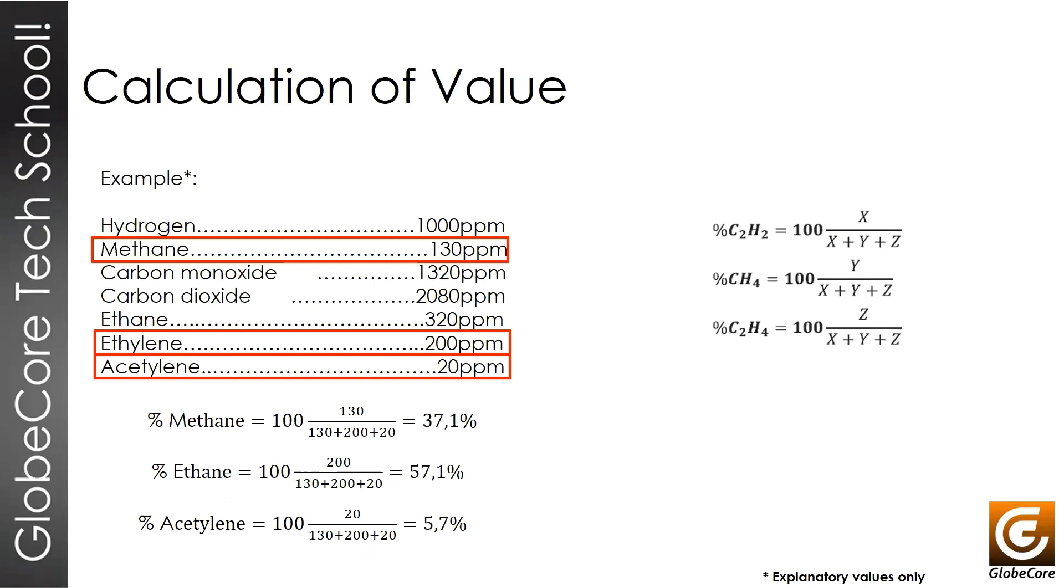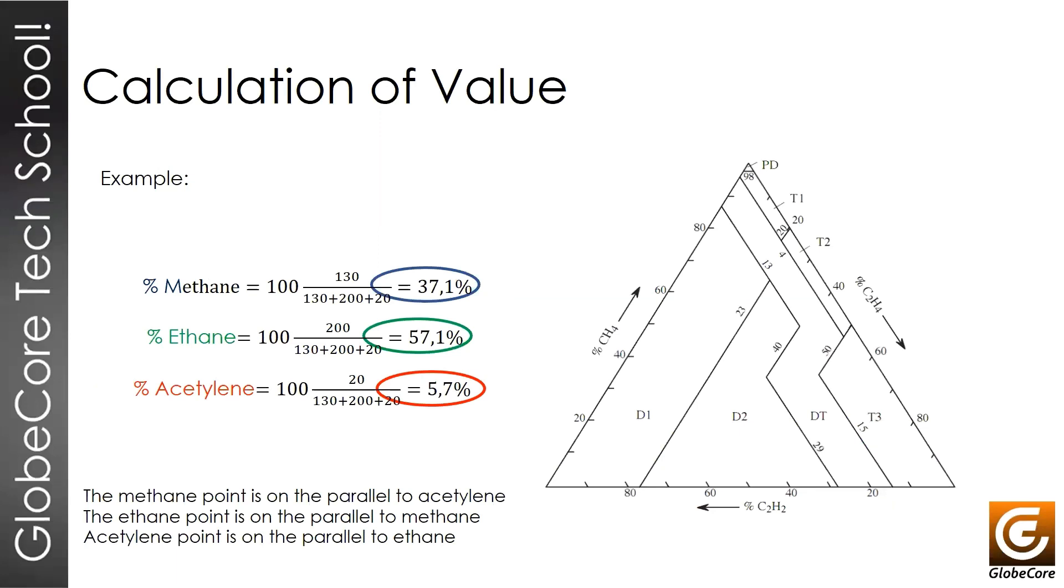When we have the correct percentages, we continue with the diagnostics and place these percentages on the triangle. We see that the concentration of methane is 37.1%. We find the corresponding point on the methane side, right there. From that point, we plot a line that is parallel to the acetylene side. This is the acetylene side at bottom, and we plot the line.